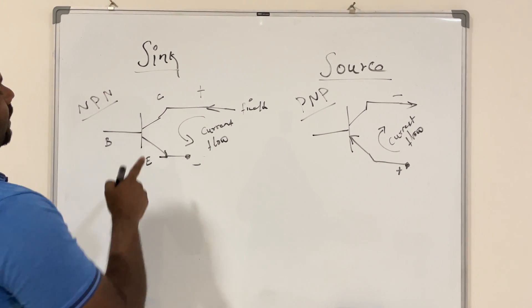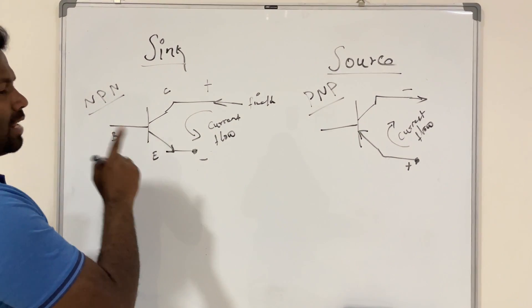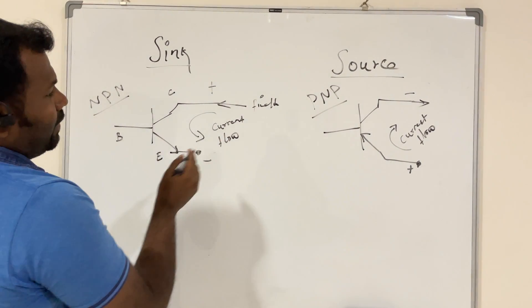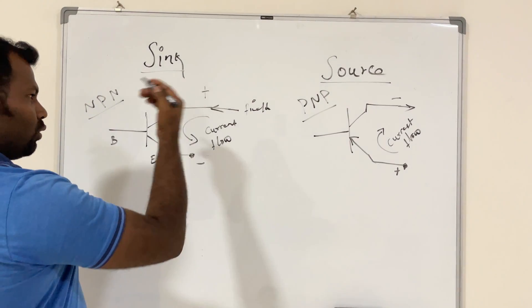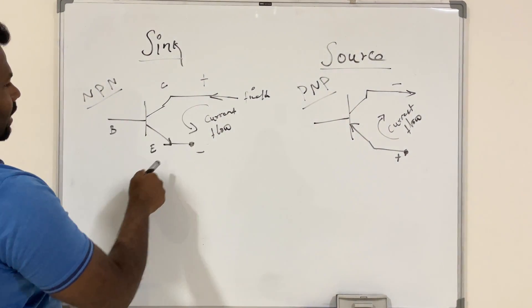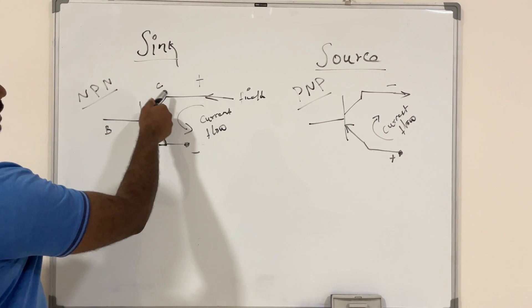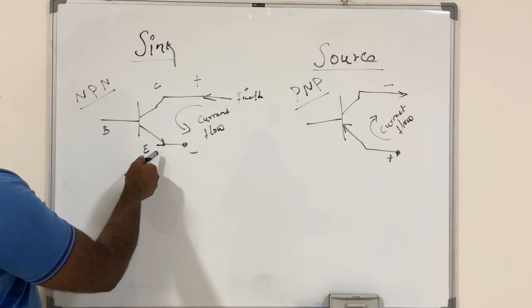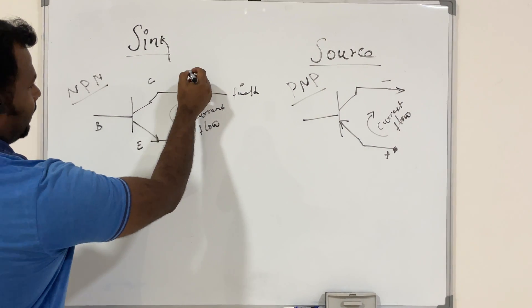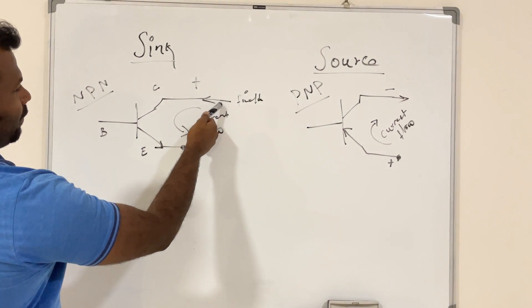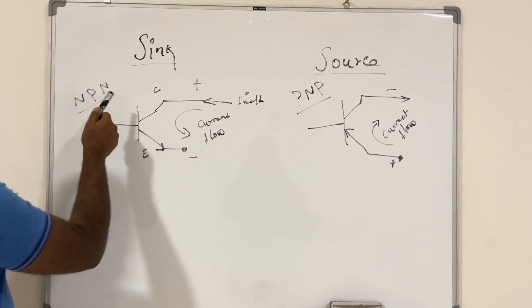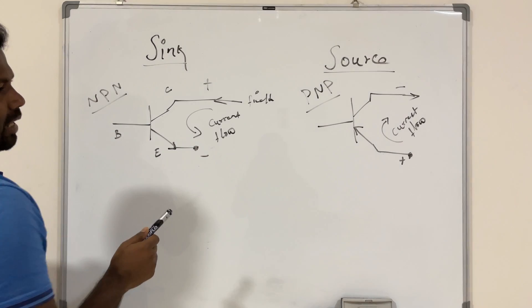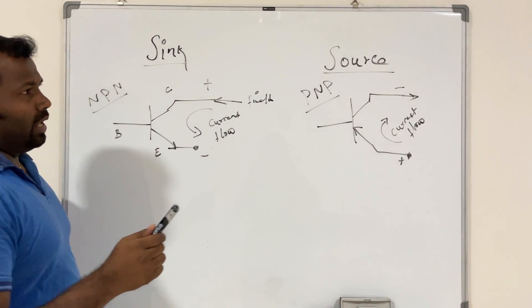Now we will see how the NPN and PNP transistors work in I/O cards. The I/O card connected with an NPN transistor is called sink type. In a sink type I/O card, the current flows from field to PLC — meaning the current sinks to the PLC. In the NPN transistor, the positive is connected to the collector side and the negative to the emitter side. The input is connected on the collector side, which is the positive side, so current flows from positive to negative and sinks to the PLC.